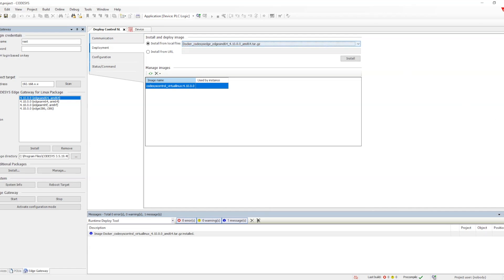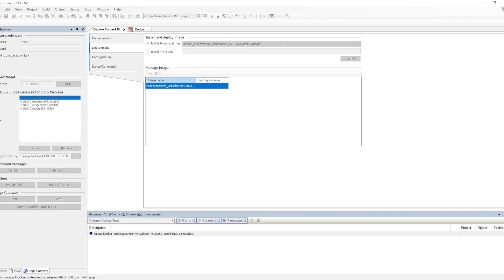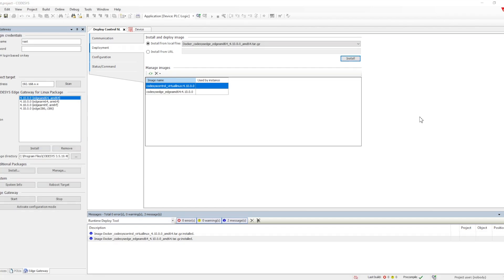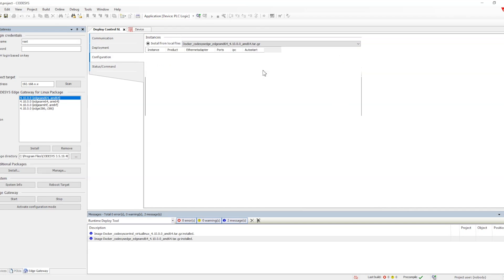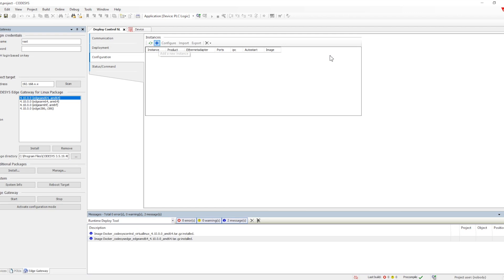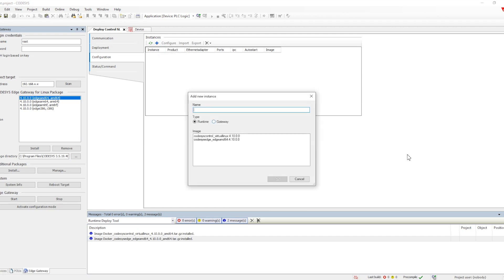The Edge gateway is the gateway through which we will be connecting to the PLC. When we select and click on install, the Edge gateway will get installed. Once both images are installed, we go to the configuration part. In configuration, we need to configure the instance and the gateway — the different instances of the PLC we want to configure and the gateway through which we will be connecting to those instances.